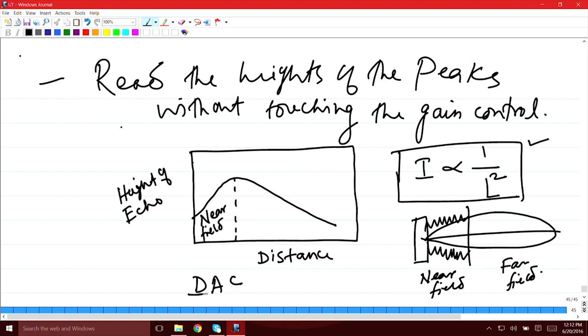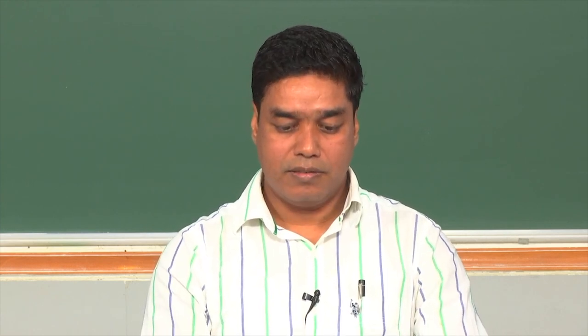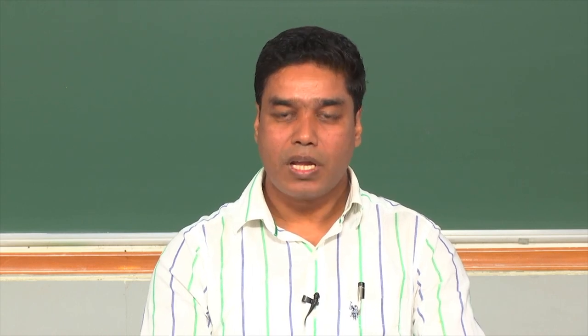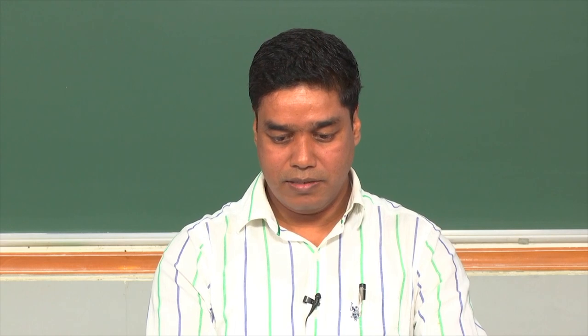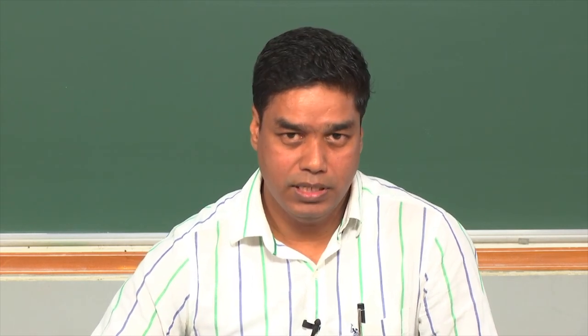That is exactly what you see in the distance amplitude curve — the increasing region corresponds to the near field. The other region is the far field, where there are no such fluctuations and signal intensity decreases as distance increases following the inverse-square relationship. That is why the DAC (distance amplitude correction) curve first increases then decreases as a function of distance.